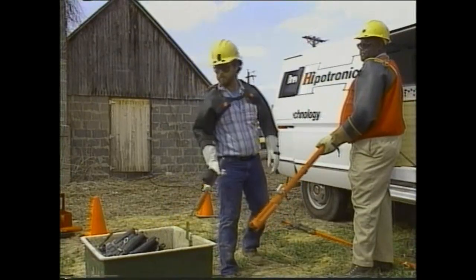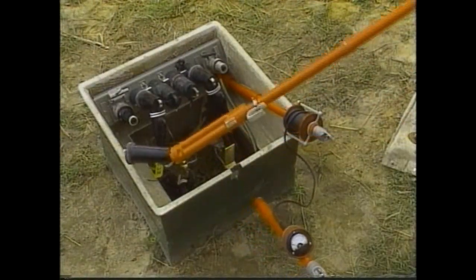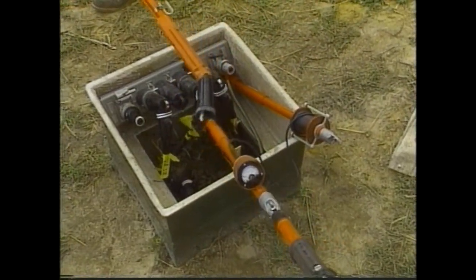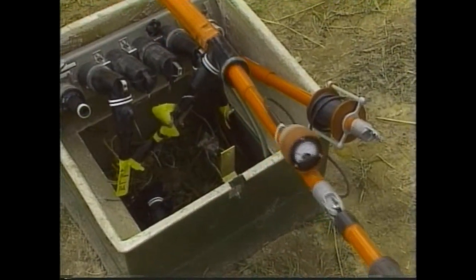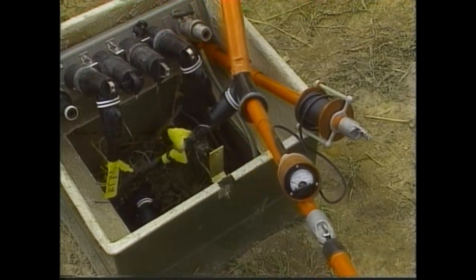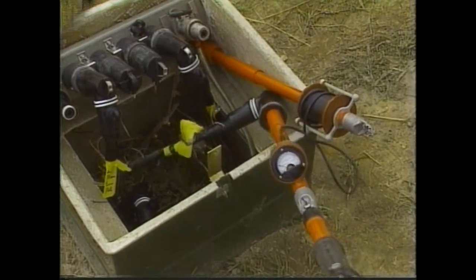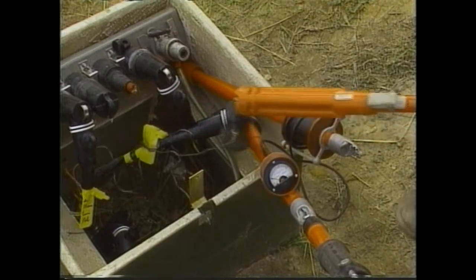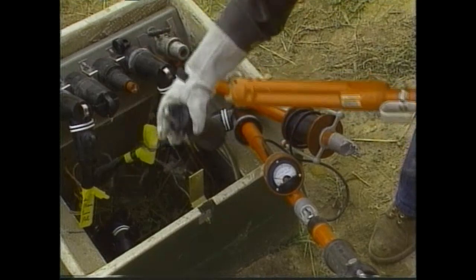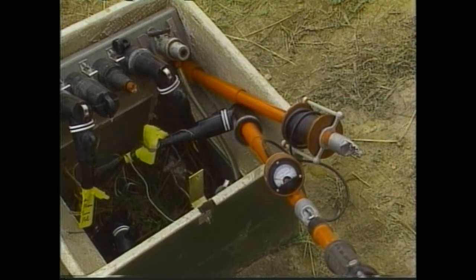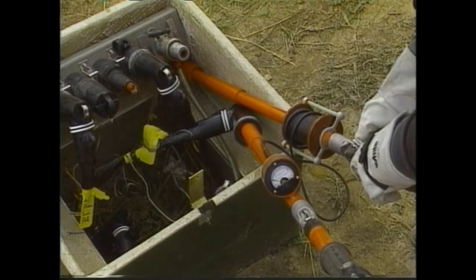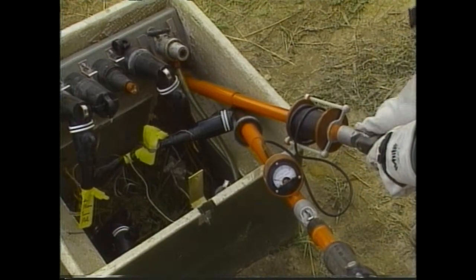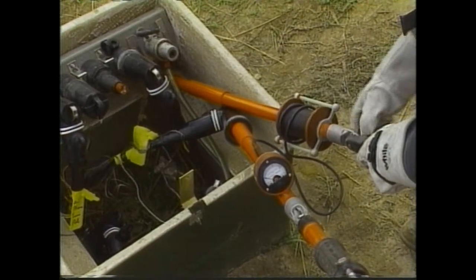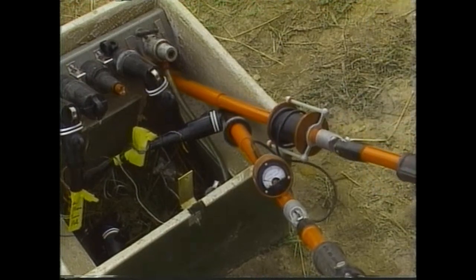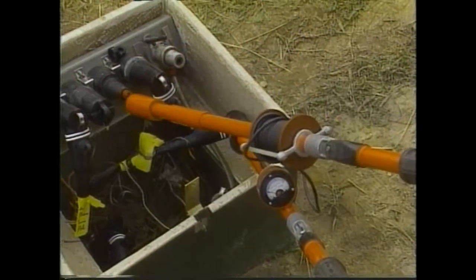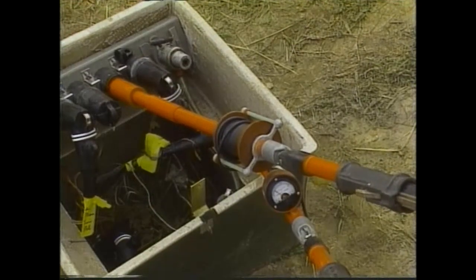It appears that the cable on the far left is the one we're looking for because the middle cable gives us a meter reading and the first cable did not. We pull the elbow on the suspected cable and make one more test before we ground it. We use another type of voltmeter on a shotgun stick to test for voltage and confirm the fault. We attach the elbow to one end of the meter. Then we remove the protective device from the energized circuit. We attach the shotgun stick to the other end of the meter. And place the second shotgun on the energized circuit. An upscale movement of the meter indicates a fault.